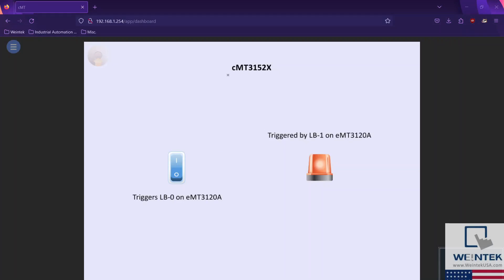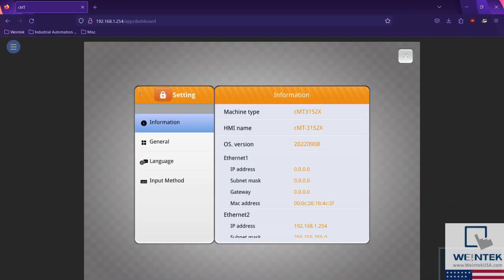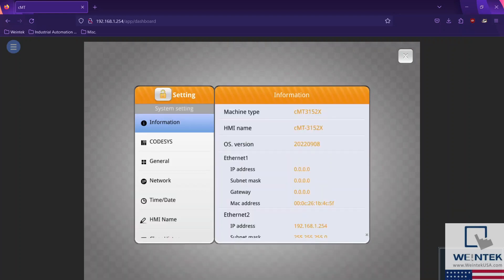In our CMT series HMI, the settings button is located on the top left of the HMI screen. To edit network settings, select the lock icon and enter the HMI's password. The default password for all Weintek HMIs is 111111.